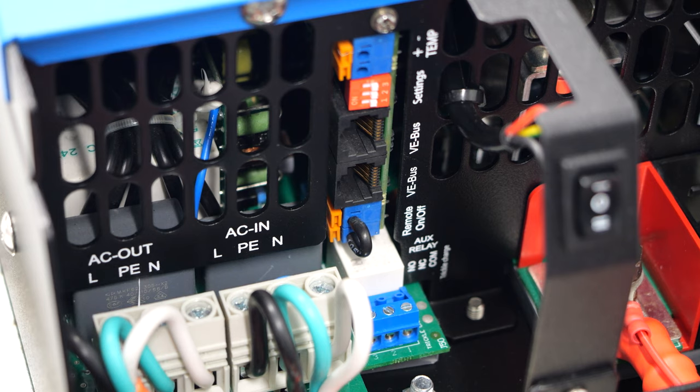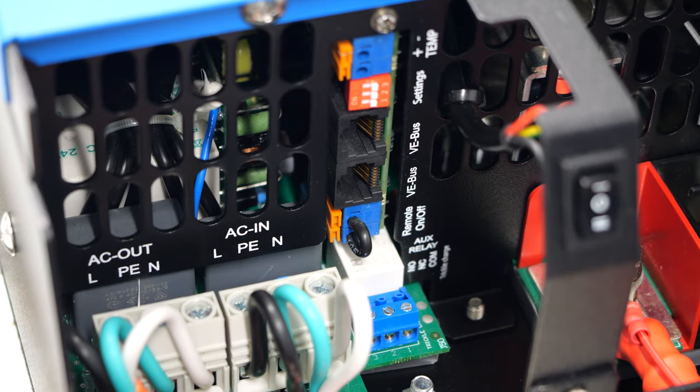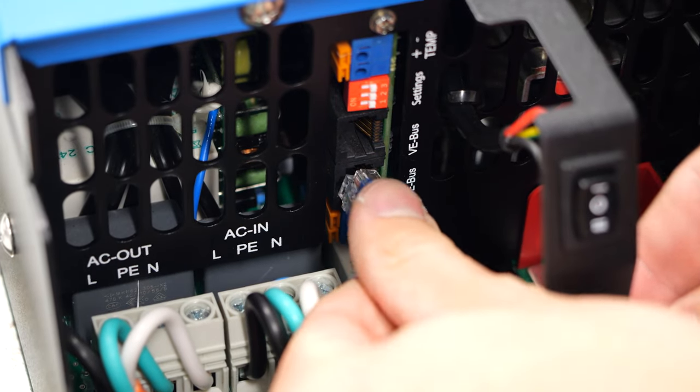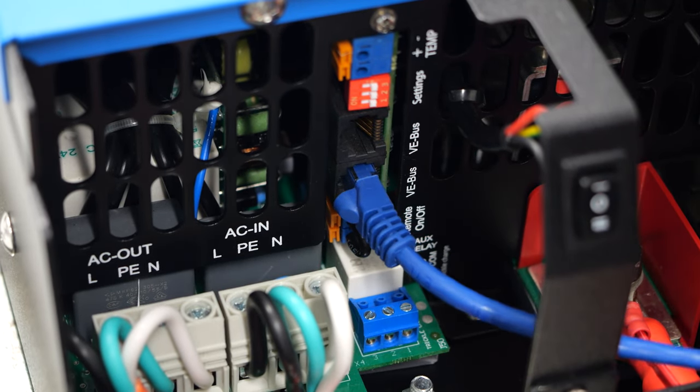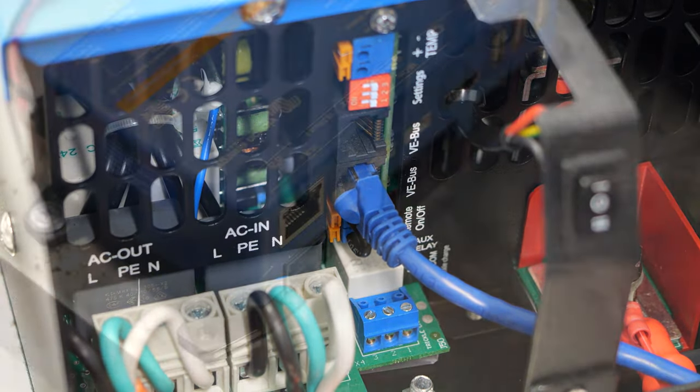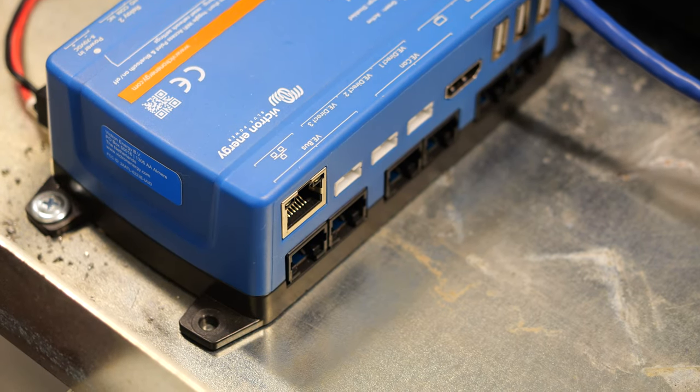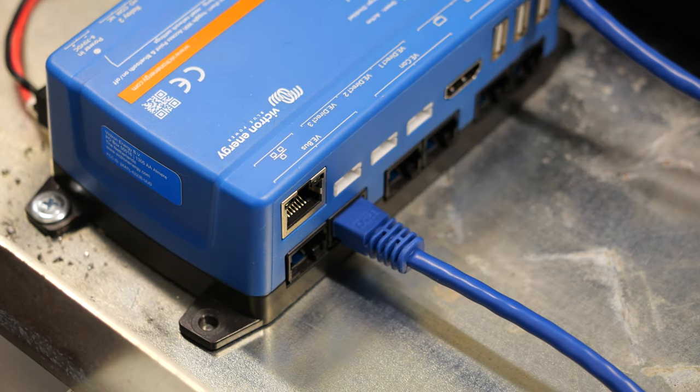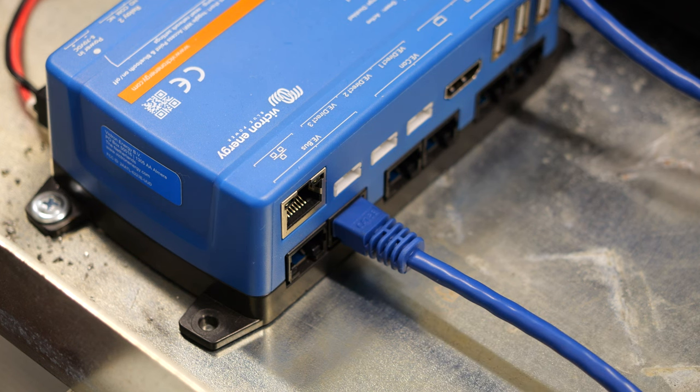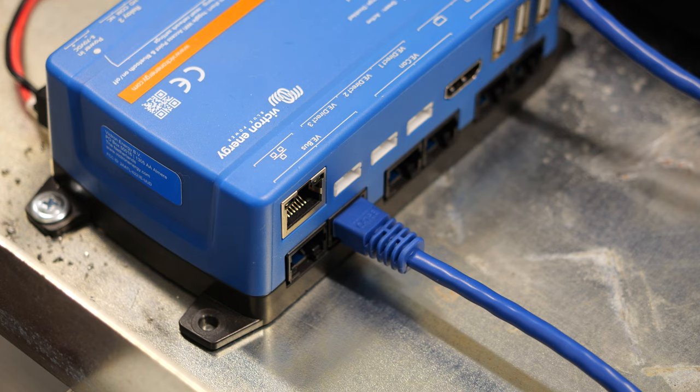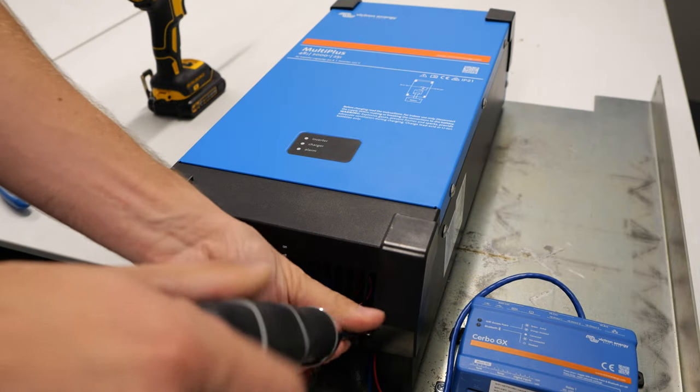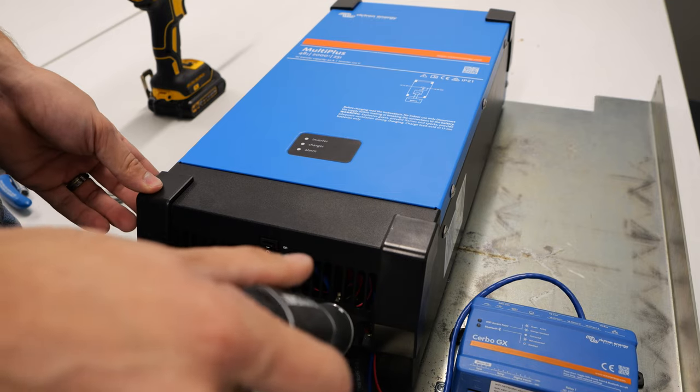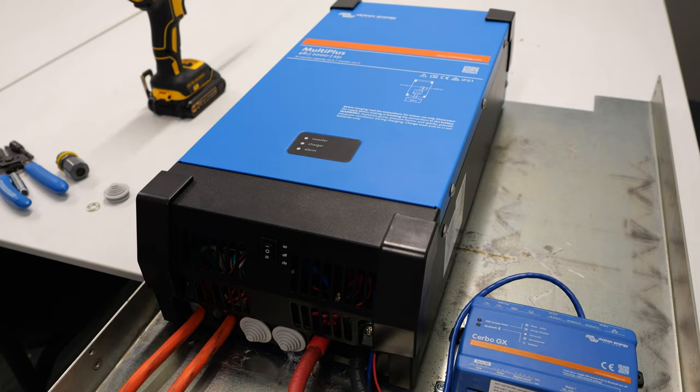All that's needed now is to set up the communication between the inverter and the Cerbo GX. I have just a standard network cable here. I'm going to plug it into one of the VE bus ports in the inverter, then on top of the Cerbo GX into any of the corresponding VE bus ports. The unused ports don't need anything in them, no terminators or anything like that. Now all that's left to do is throw on the bottom cover and tighten up the two screws.